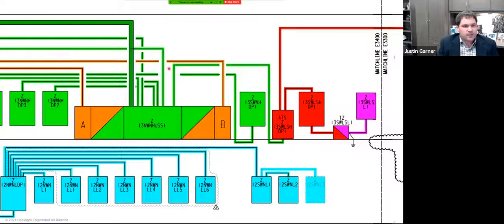You'll notice here that anything that's in green is normal power only. It would only be fed from a utility source. So it's not tied to the emergency system. Whereas we see our ATS here, it has a normal source here, and then it has an emergency source coming from that paralleling gear that we showed earlier, feeding into this ATS.